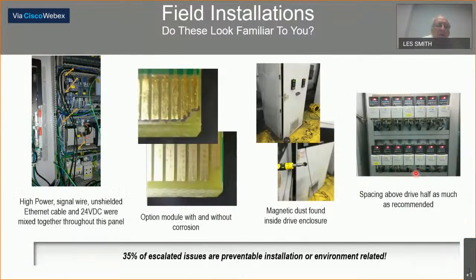On installations, does this look a lot like your plant? And you can tell here, and over here, it looks like an explosion in a spaghetti factory where you got wires running everywhere. And this may not happen initially, but in troubleshooting, you pull the duct covers off and the wires start to go all over. And this gets sensitive wires too close to power wires. You can see the black and the blue, which would be 480 volt and 24 volt. They get close together, and they can, in fact, transfer noise from power to control and cause headaches.